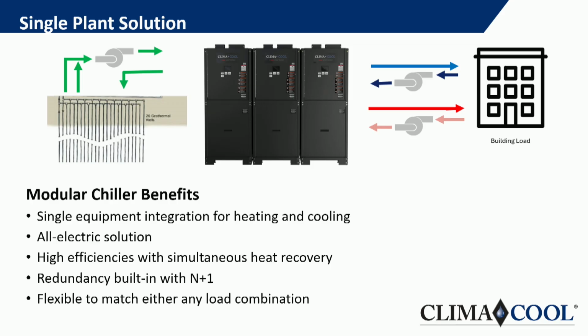And what I think is nice about the smaller systems, I'm talking about the 20 to 100 ton individual units, is it's really a nice system that can work for a lot of different applications where you have a base simultaneous load. You get a lot of redundancy, and then you're ultimately able to match whatever load diversity you have in the building. And really the impact of the ground loop is just the net difference of your loads.